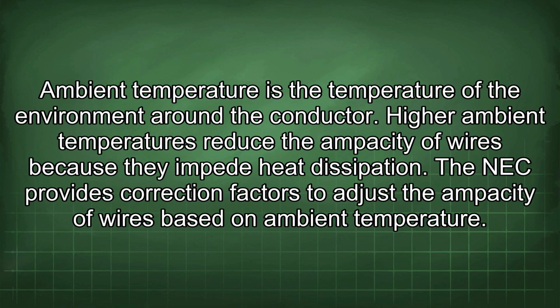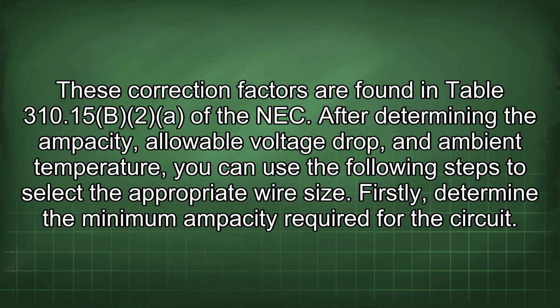Ambient temperature is the temperature of the environment around the conductor. Higher ambient temperatures reduce the ampacity of wires because they impede heat dissipation. The NEC provides correction factors to adjust the ampacity of wires based on ambient temperature. These correction factors are found in Table 310.15(B)(2) of the NEC. After determining the ampacity, allowable voltage drop, and ambient temperature, you can use the following steps to select the appropriate wire size.